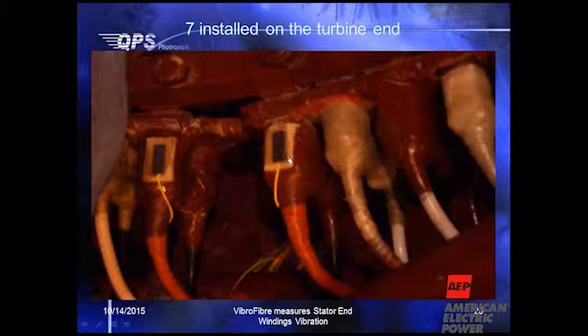When the resin cures, it becomes a whole block along with the sensor, coupling to the end winding as a complete structure. It couples extremely well. The problem of doing that is that it takes 8 hours for the resin to cure, but it did a very good job.